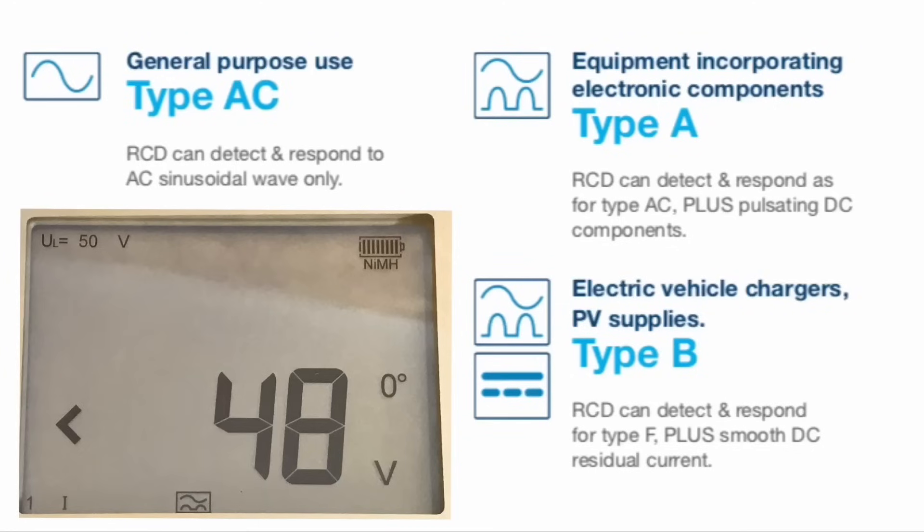Moving forward, electrical vehicle charging where any smooth DC fault current is less than 6 milliamps. But I would always advise: check the manufacturer's instructions to see what they would recommend to install. We're seeing as the 18th edition develops that the AC RCD is really being phased out for domestic dwellings. However, we should check the manufacturer's instructions when installing something that may have pulsating DC in it. Hager, Wylex, Crabtree and others are starting to insert A-type RCDs within their dual RCD boards, and that's something we've seen more and more now.